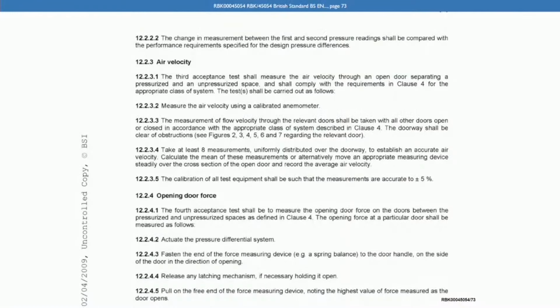We can see that from clause 12.2.3.3 in that section. So 12.2.3.3, it says the measurement of flow velocity through the relevant doors shall be taken with all other doors open or closed in accordance with the appropriate class of system described in clause 4. The doorways shall be clear of obstructions, and then you're to see figures 2, 3, 4, 5, 6 and 7 regarding the relevant door. Now, did you understand that that door reading needed to be taken with a combination of other doors open?